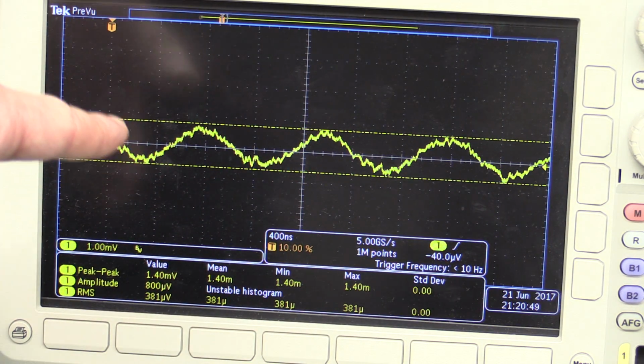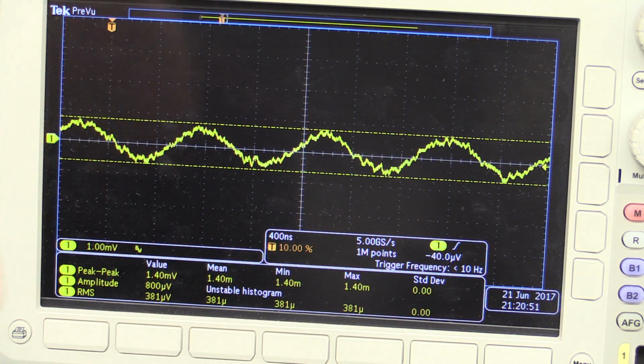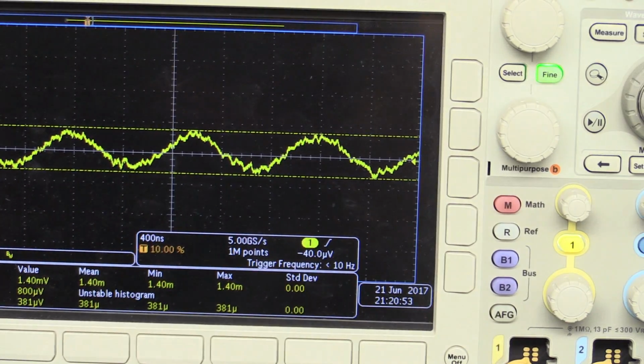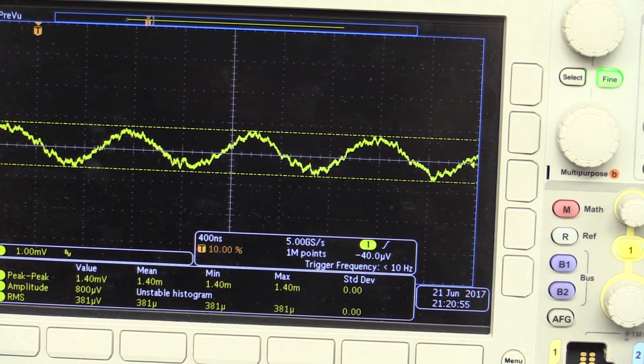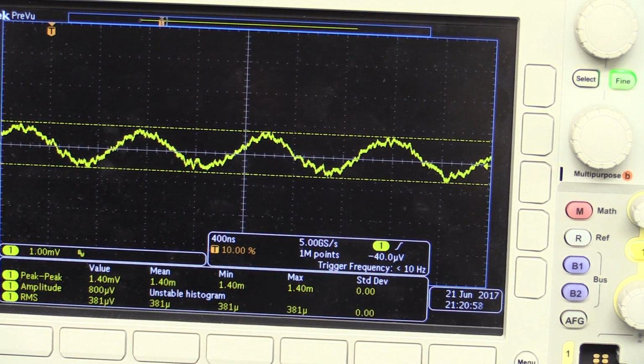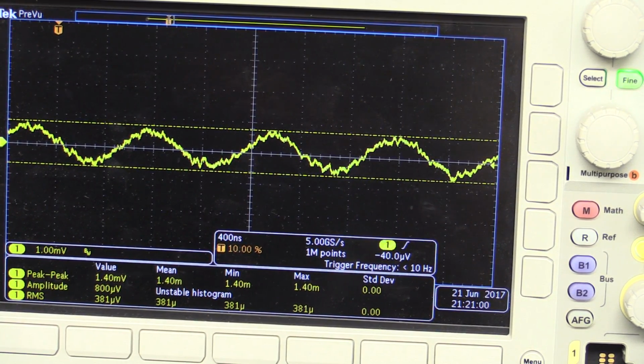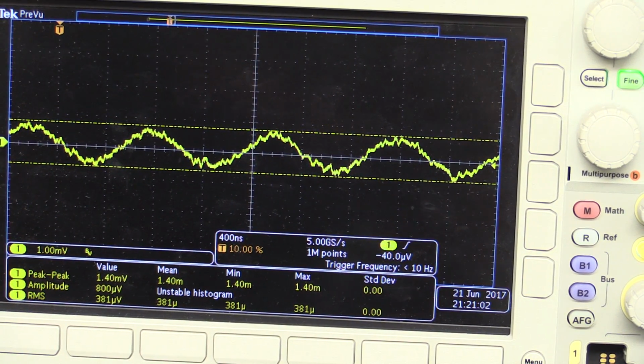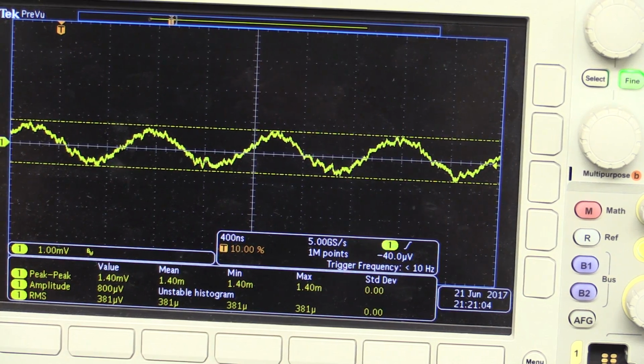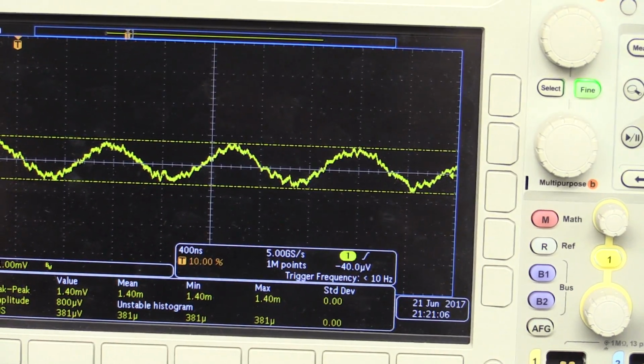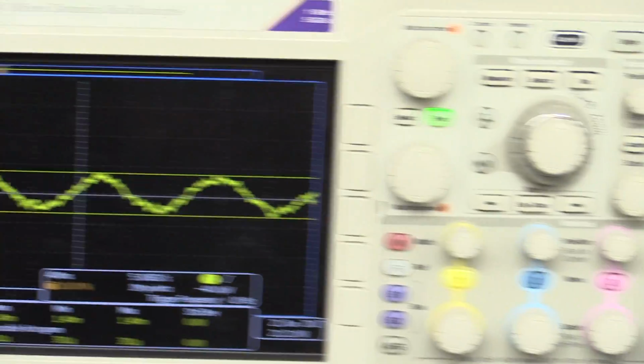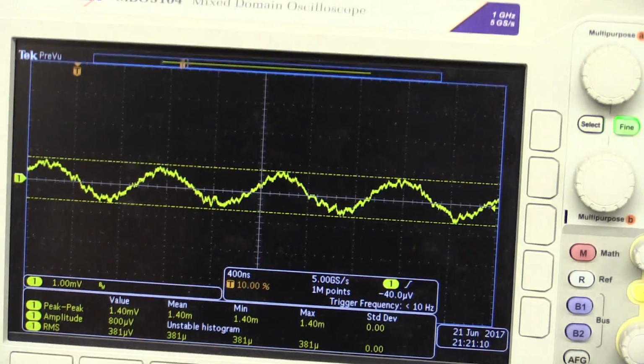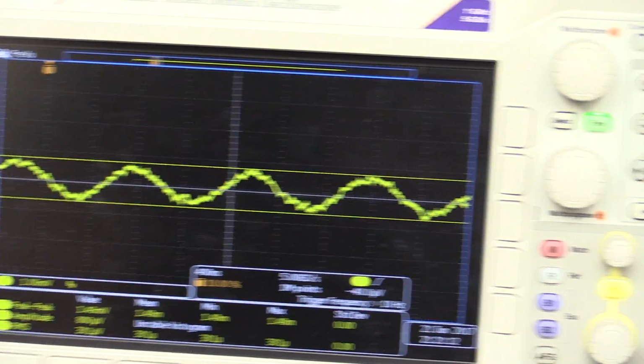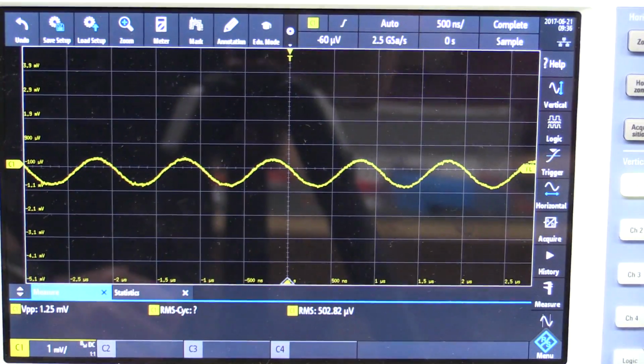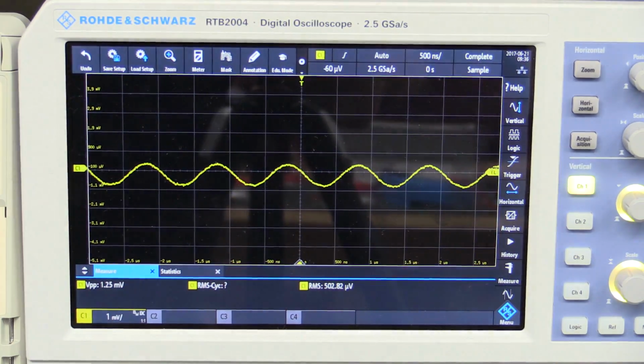Look at it. You'll see that other scopes are much better. So this is only 1 millivolt per division minimum, but there's a lot. Oh, by the way, this is a 1 megahertz sine wave, and all the scopes are set to 20 megahertz bandwidth limit and the same memory depth of 1 meg. There's no averaging or anything else turned on. So yeah, the Tektronix MDO 3000, really noisy. I don't know where that's coming from. And you'll see that in the contrast of this Rohde & Schwarz RTB 2004.